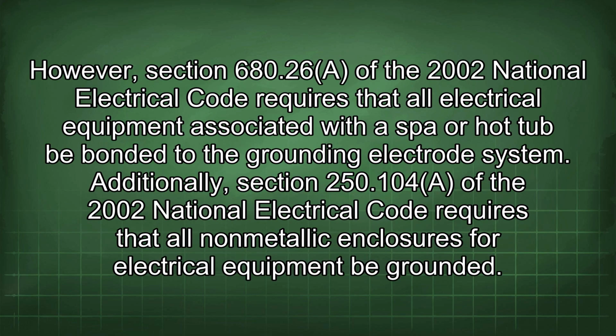However, Section 680.26 of the 2002 National Electrical Code requires that all electrical equipment associated with a spa or hot tub be bonded to the grounding electrode system. Additionally, Section 250.104 of the 2002 National Electrical Code requires that all non-metallic enclosures for electrical equipment be grounded.